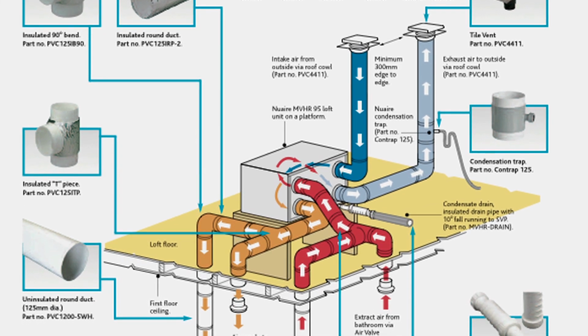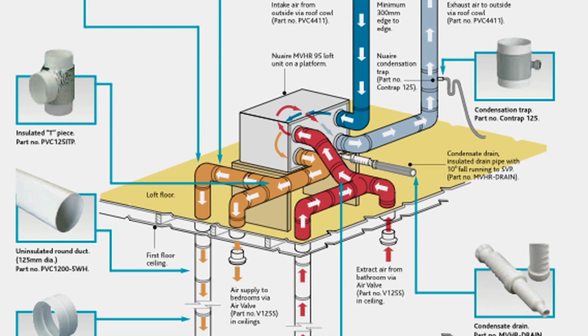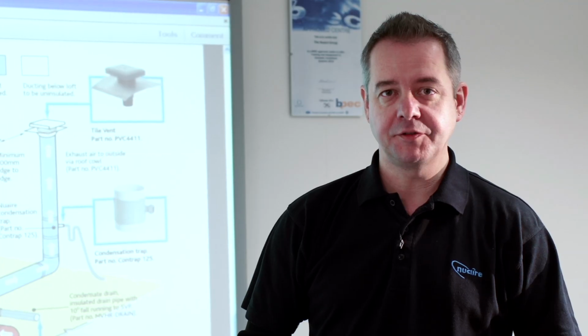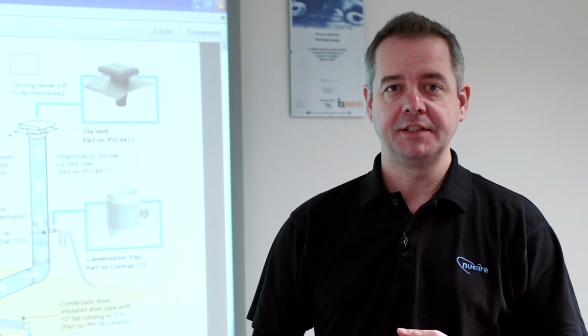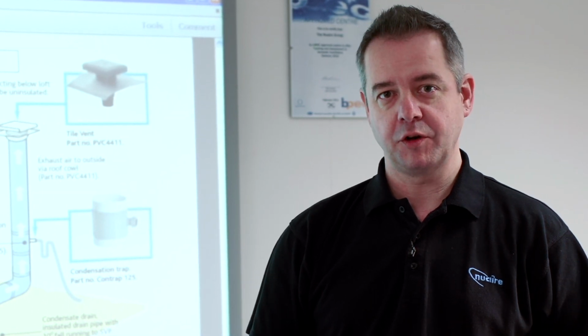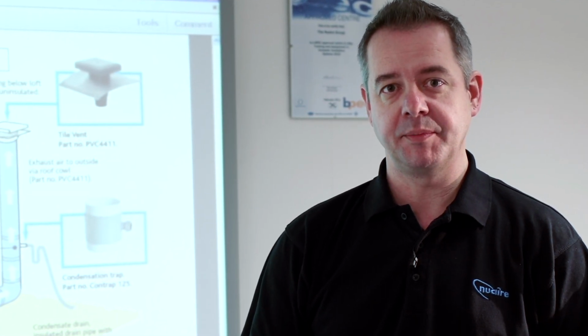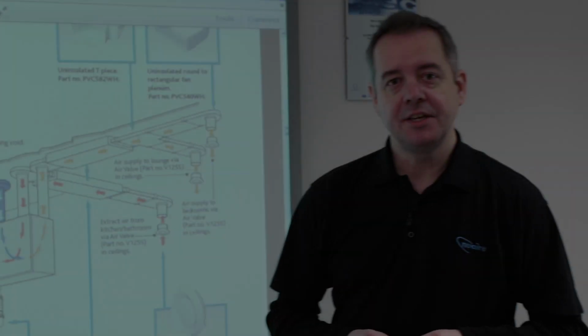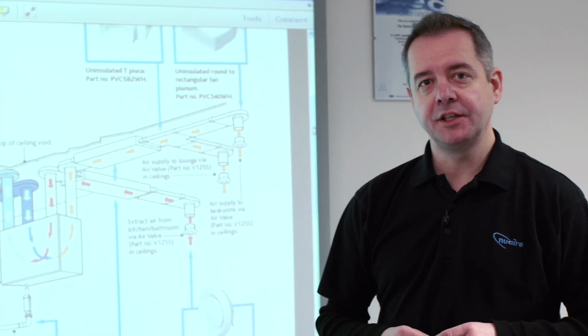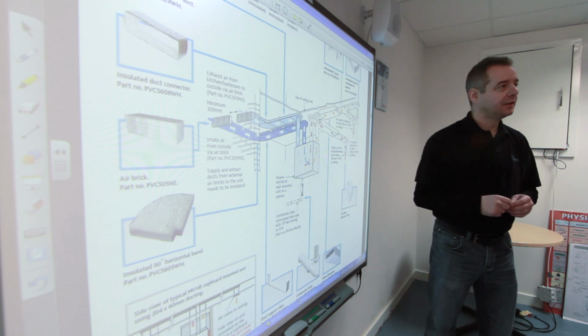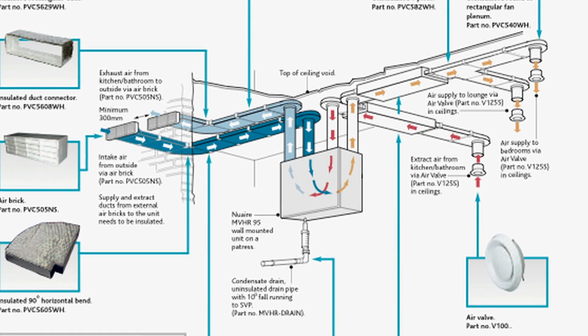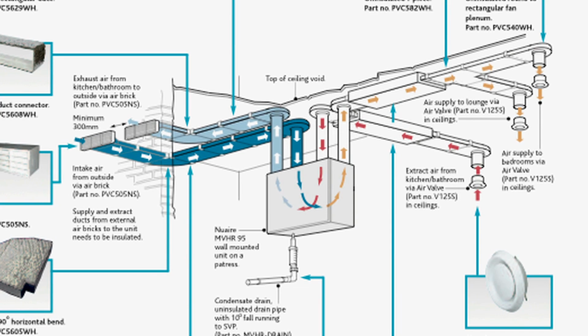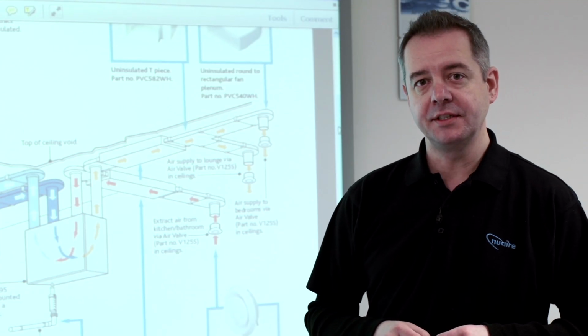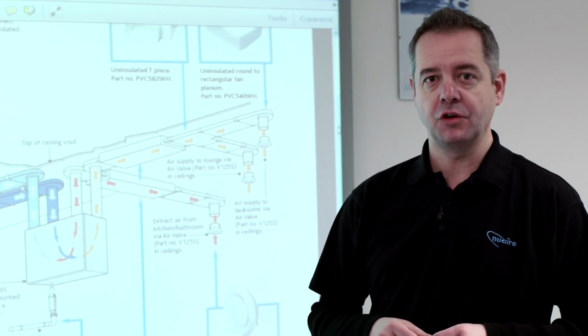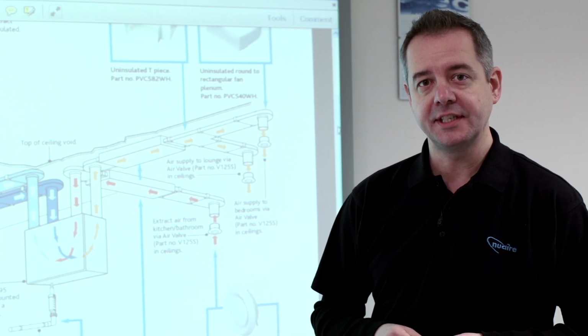Any ducting that passes through an unheated space, such as a loft, must be insulated. This is for two reasons. Firstly, it increases the efficiency of the system, and secondly, it prevents condensation from forming on the outside and causing potential damage to the building. In applications such as apartments where it's necessary to run the ducting within the ceiling void, a critical element is to make sure that the ducting that runs to external is insulated, again for the same reasons, for energy efficiency and to prevent condensation on the outside of the duct and potentially damaging the building.